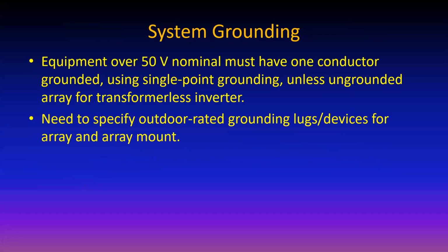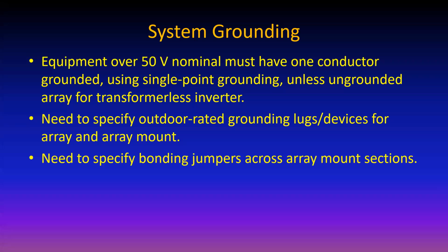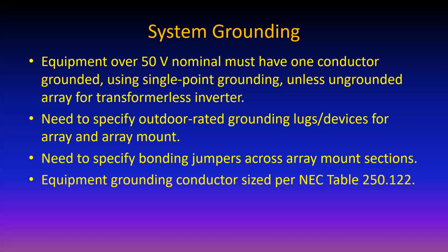Grounding, if you're over 50 volts, you have to have all your components grounded, like your array metal, the array mount metal ones, the frames of the modules, and anything metallic has to be grounded with grounding lugs. Okay. Need to specify bonding jumpers across array mount sections. The people who manufacture the arrays, they give you the sheet that tells you exactly how you have to bond from one section to another. And some of them, you snap them together and they take care of the bonding. You don't need any additional bonding jumpers. So look at the specs on the array mount to see whether you need any additional jumpers. Equipment grounding conductor, 250.122 gives you that.